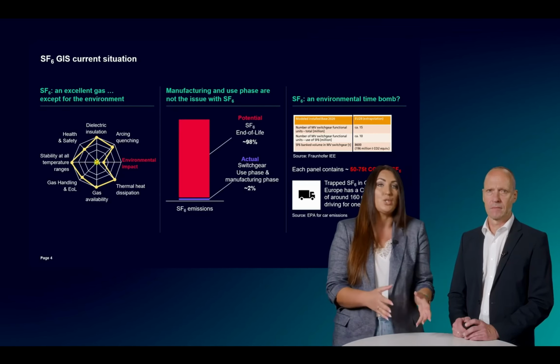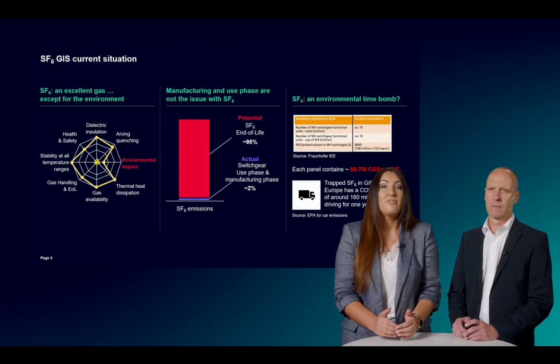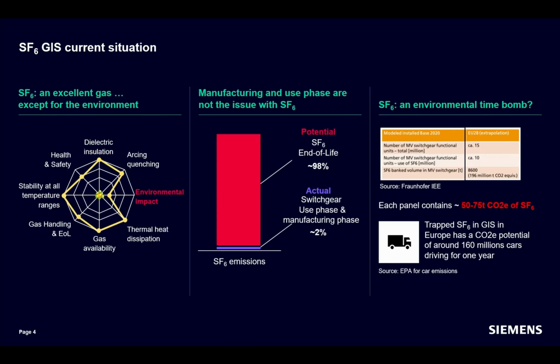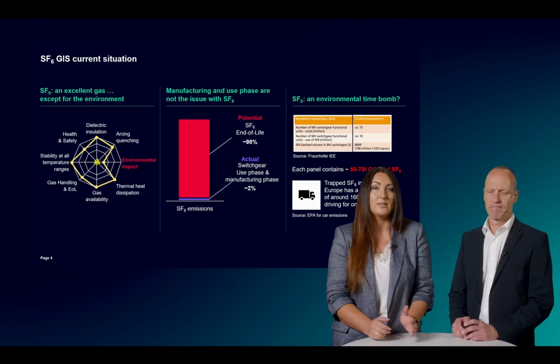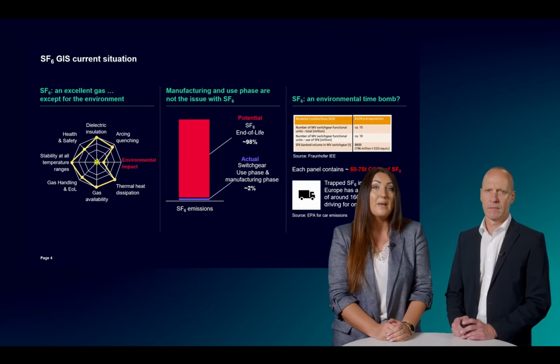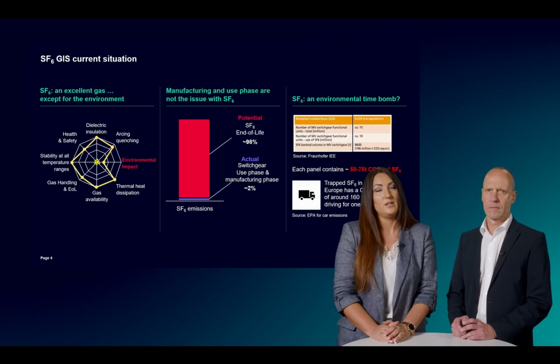Now considering that each switchgear panel contains around 50 to 75 tons of CO2 equivalent of SF6, and considering the overall number of medium voltage functional units using SF6, if we take, for example, the European installed base, we can easily get the comparison that trapped SF6 in the GIS in Europe has a CO2 equivalent potential of around 160 million cars driving for 1 year. This value is, of course, theoretical, as SF6 remains in the hermetically sealed stainless steel vessel throughout its operational lifetime. But it is a very important aspect, the end-of-life handling of SF6 gas and the recycling process, which needs to ensure that no SF6 is released into the atmosphere.